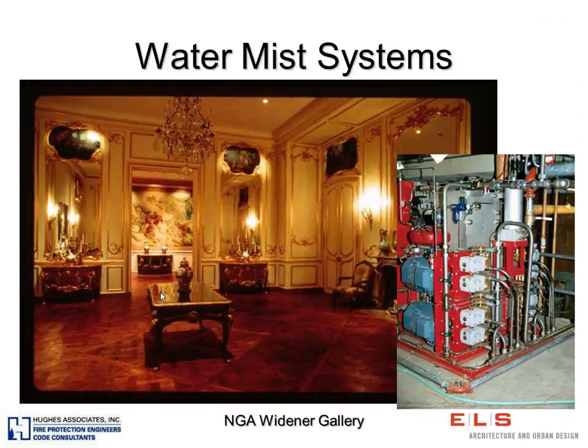So, water mist systems. This is the National Gallery of Art Widener Gallery, and looking at this space, this may be before or maybe after the installation of the water mist system. I can't tell, but the way a water mist system works is that it has nozzles like a sprinkler system, but it is water. It uses a lot less water, and it's water under very high pressure. And so what you see here on the right inset is the pumping skid for the water mist system. So all of this is the pumping skid.